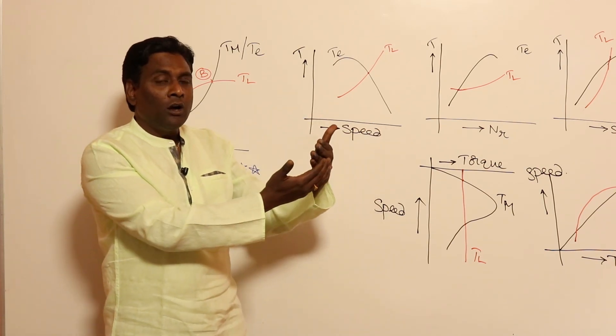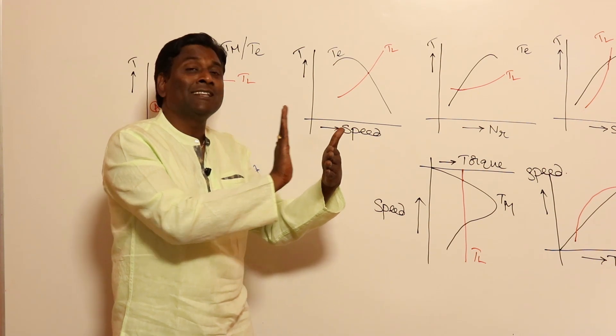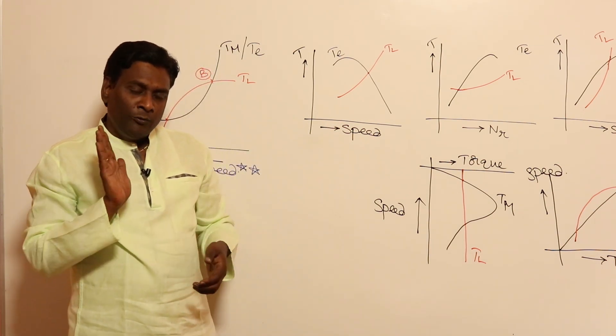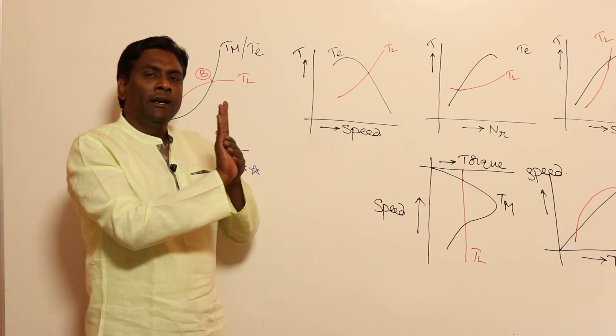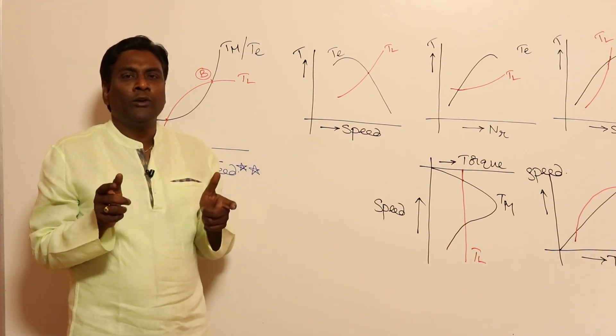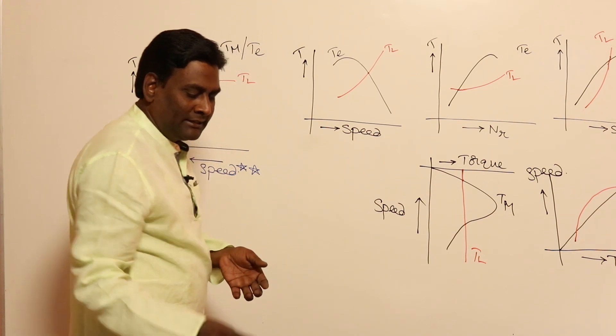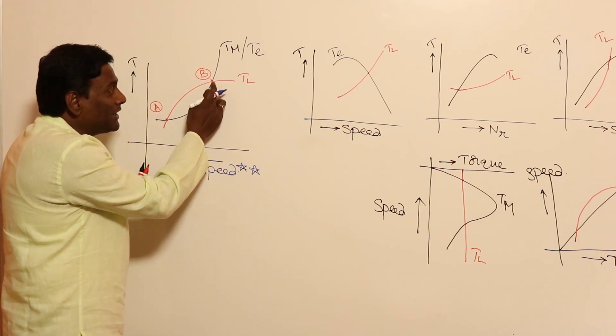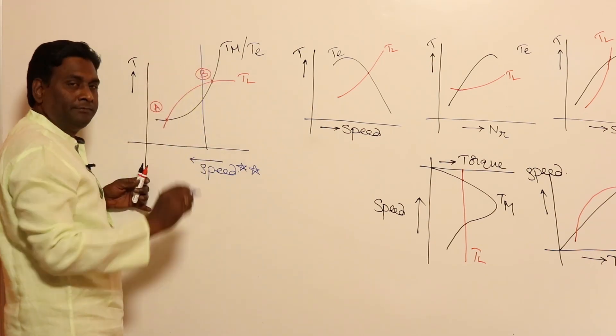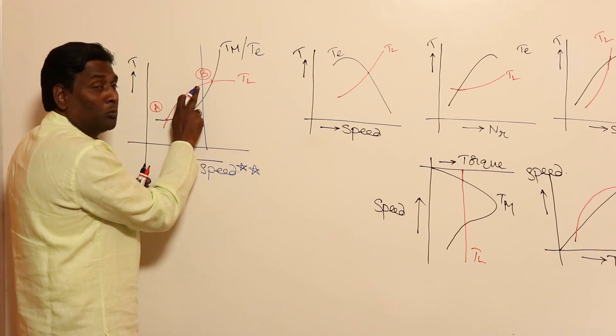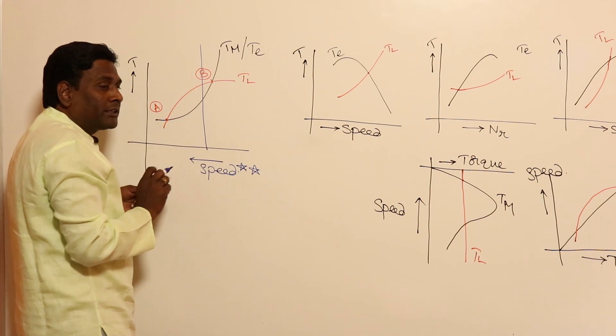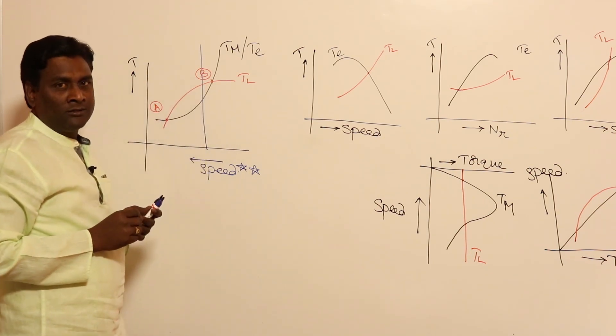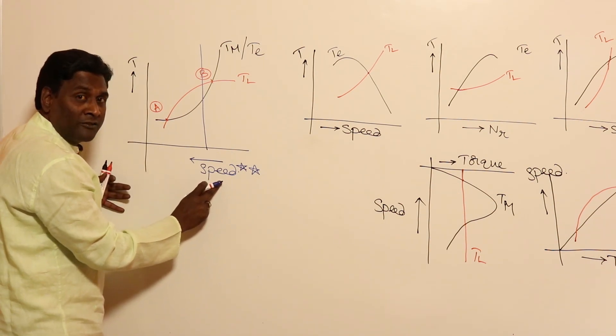If the load torque requirement is more and the motor developed torque is less — meaning opposition is more compared to the push — the motor will decelerate. When motor torque equals load torque at a given speed, it will rotate continuously at that speed. To find whether a point is stable, draw a line immediately after the junction point in the direction of increasing speed.